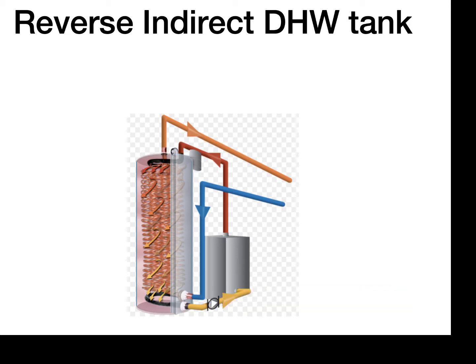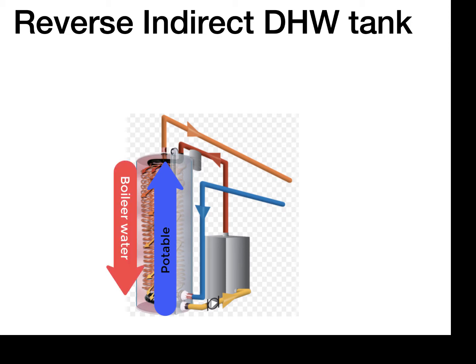This system is also a counterflow type of design, whereby the cold potable water enters the bottom of the storage tank through the copper heat exchangers, and the boiler water enters from the top of the tank, and essentially those two flows go counter to each other, with the hot water going down and the potable cold water coming in from the bottom and going up and picking up heat from the heat source itself.